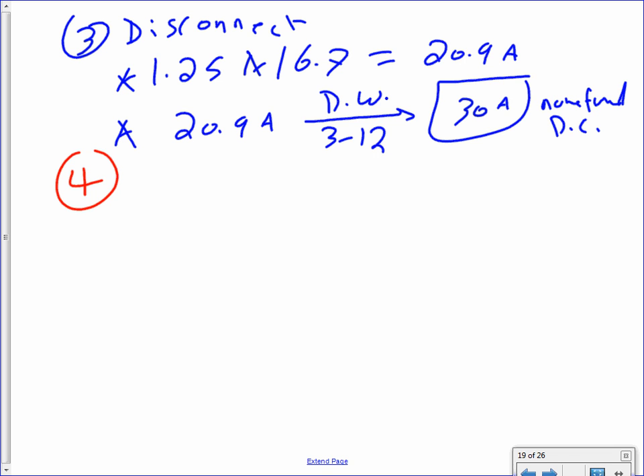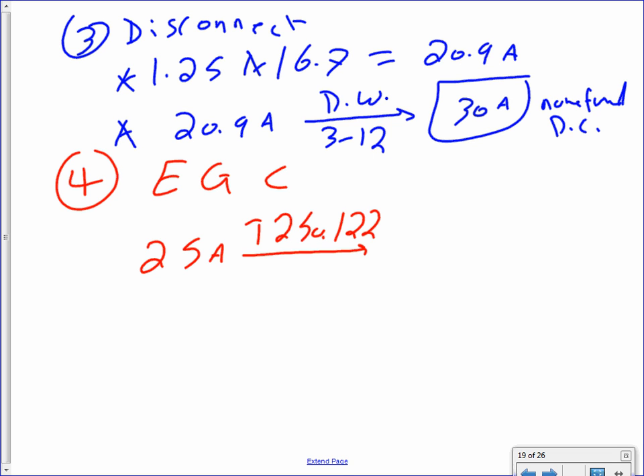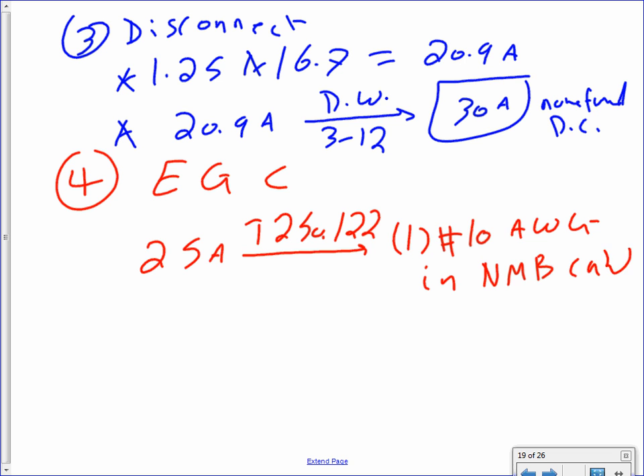Number four is the equipment grounding conductor. That's a piece of cake. My overcurrent protection was 25. You take the 25 amp to table 250.122. Would that give me number 10? Anybody? With 25, I believe it's number 10. Number 10. There you go. 25 amp is number 10. So this is also going to be one conductor number 10 AWG in an NM cable. That will be part of your NM cable.